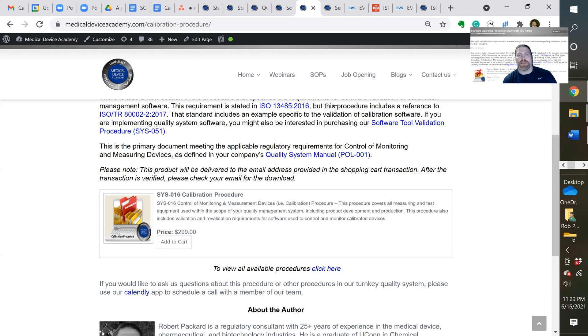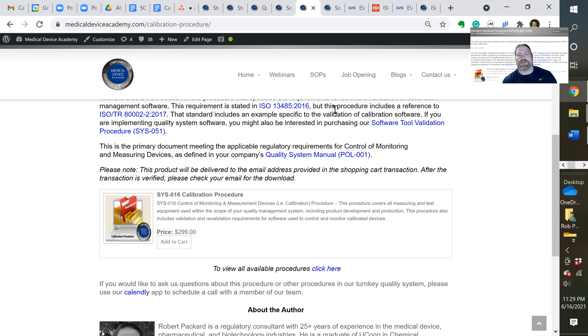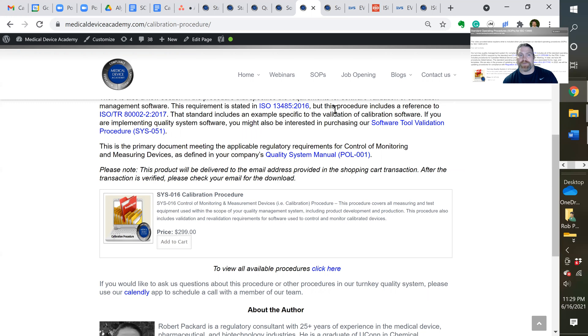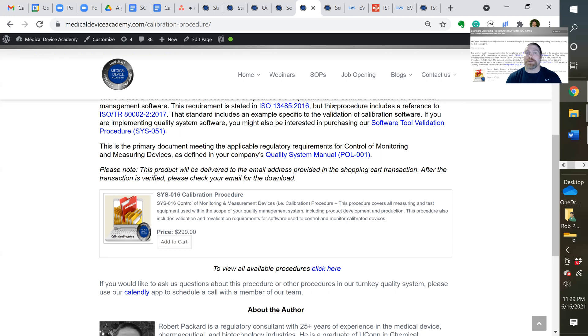But if you're going to get a little bit tougher here, what about the Canadian requirements? Well, there isn't a specific requirement in the Canadian regulations for calibration, because Health Canada requires that you become ISO 13485 certified. So they only rely on certification to the 13485 standard.